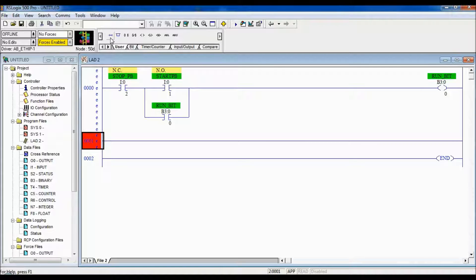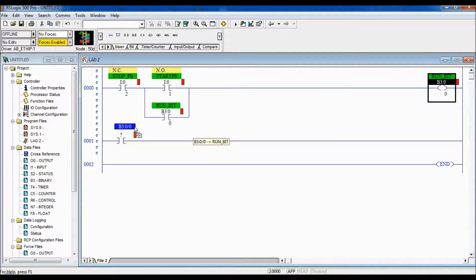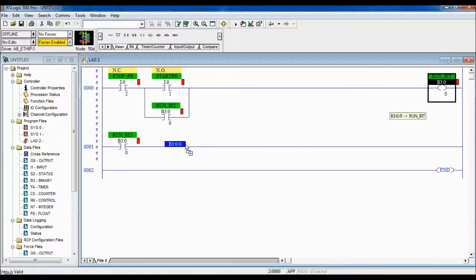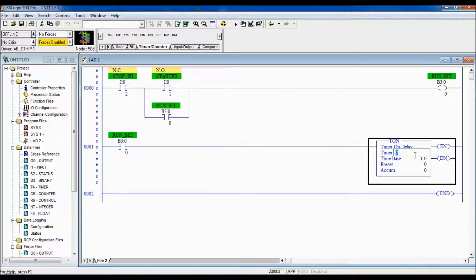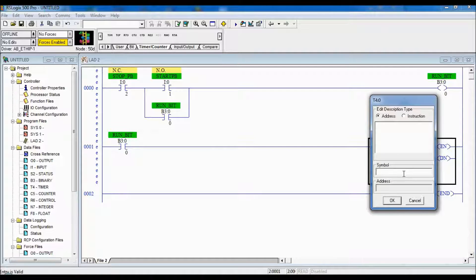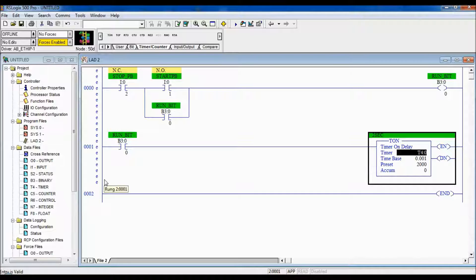Once the start button is pressed and the run bit is true, the coolant starts right away, and we also need to start a timer. When the run bit is true, I'm going to start a timer. I'll grab the B3 run bit address and add a timer instruction at T4:0 — this is my 2-second timer. Using a time base of 0.001, I need a preset of 2,000 to obtain 2 seconds. When the run bit is true, this timer begins timing.